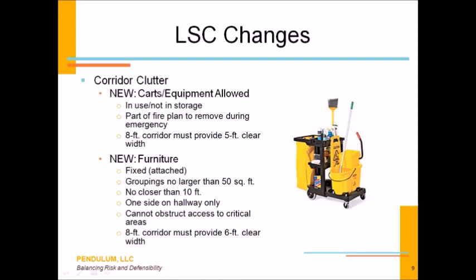This has been a big problem. I work with facilities around the country, and every state seems to do it a little bit differently. In some states, if a surveyor is in your building and they see an item there on one side or the other for more than 3 minutes, they used to cite you for the presence of corridor clutter. If they would see things on both sides of the corridor, they're going to cite you because everything, as you know, needs to be to one side. But you are now allowed to have those items in that corridor for an unlimited amount of time, providing that they are not pieces of equipment that are in storage. So if you've got that med cart, that lift, that housekeeping cart that might be in use and present in that corridor for 10, 15, 20 minutes or longer, as long as it's being utilized and not in storage, it's allowed to be there. Again, keeping everything on one side and maintaining 5 feet of clear width.